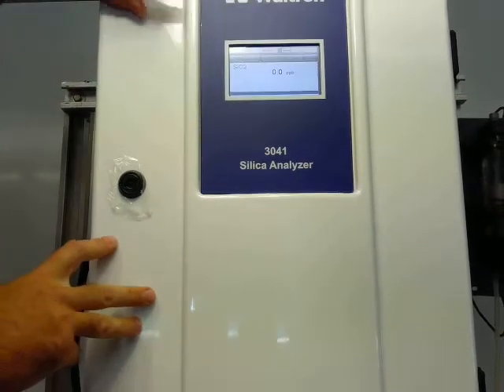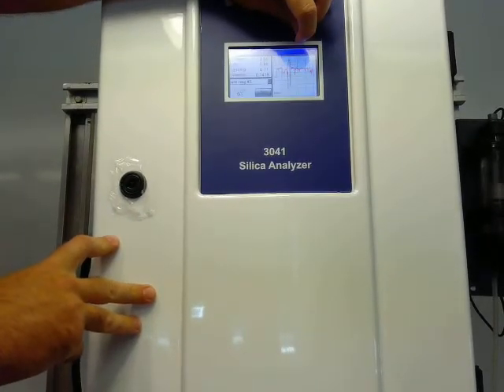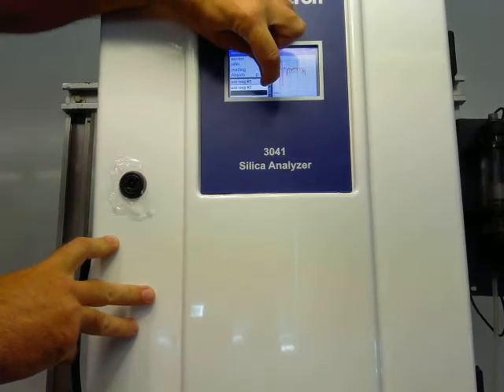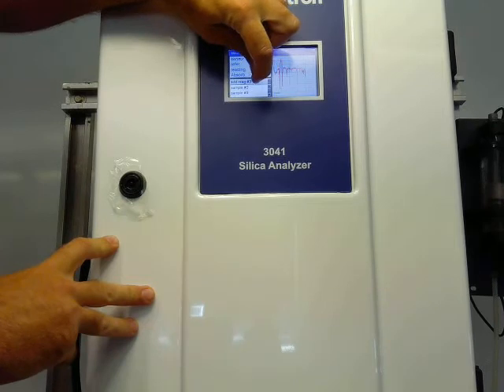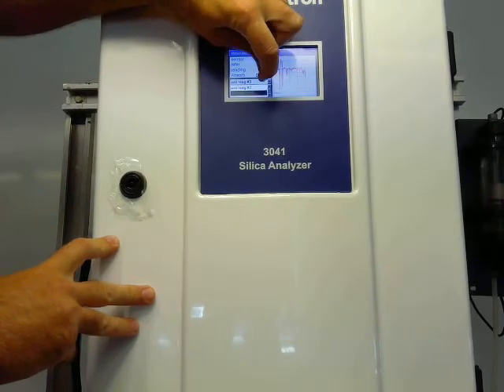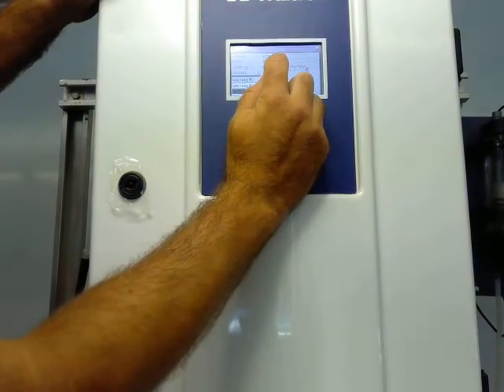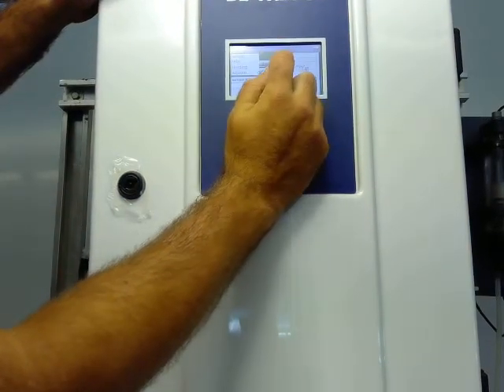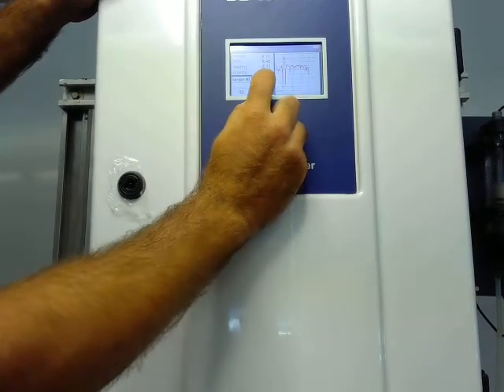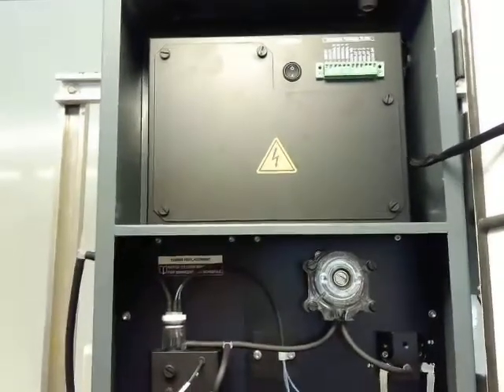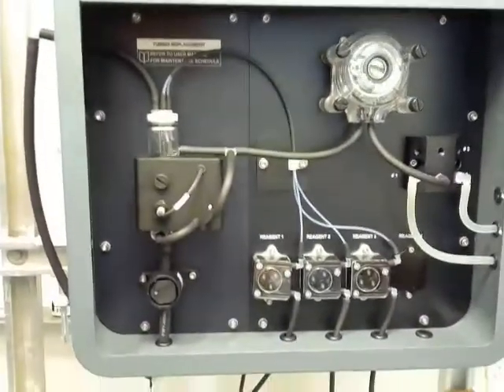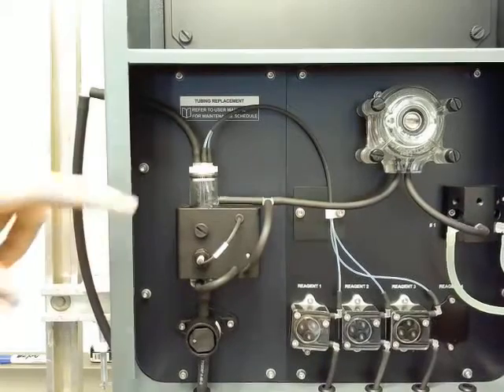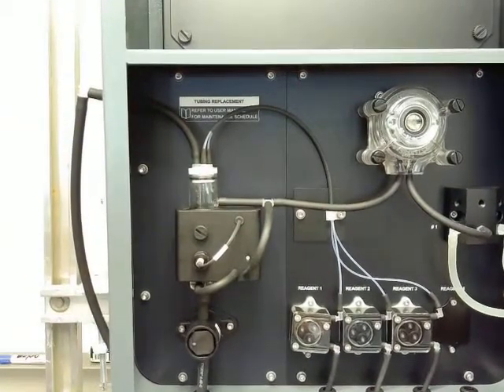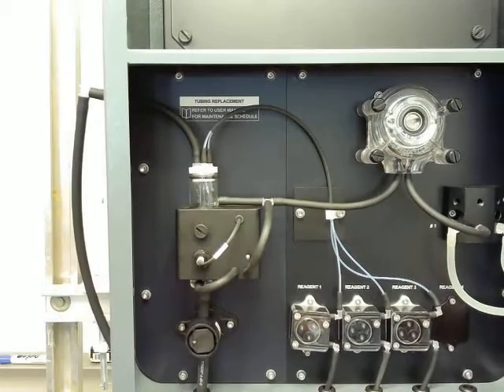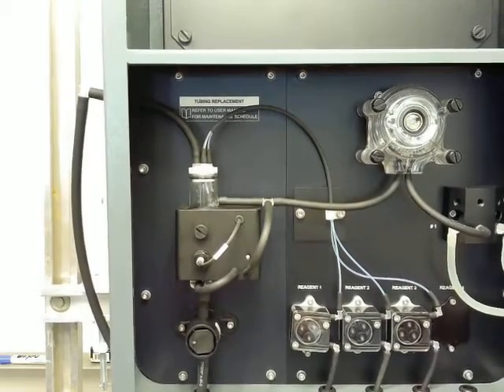So if we come to our main screen, we would go into our display menu, same as we did for our reagent prime, and hit the manual button. And then on this drop-down list, there are various commands, one of them being add sample. I'm going to add sample for about 25 seconds, and then hit on. And now we should see the sample pump turning. It should be drawing sample into our flow cell. So that's a good indication that we did the sample pump tubing placement correctly and everything's working well.